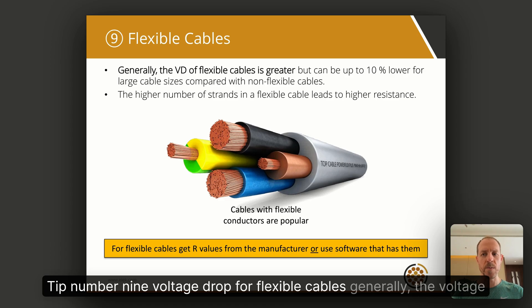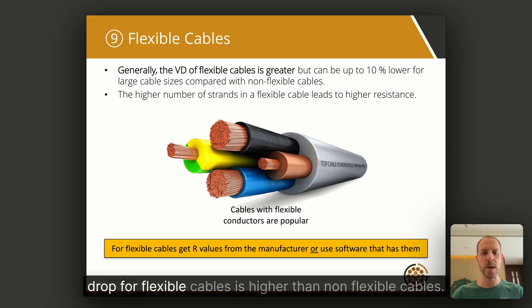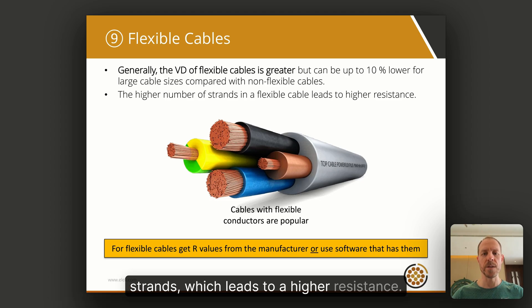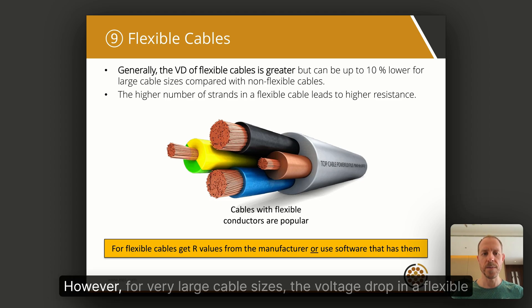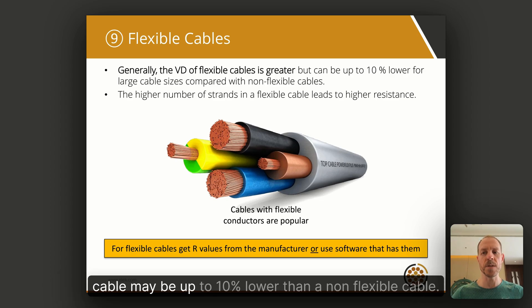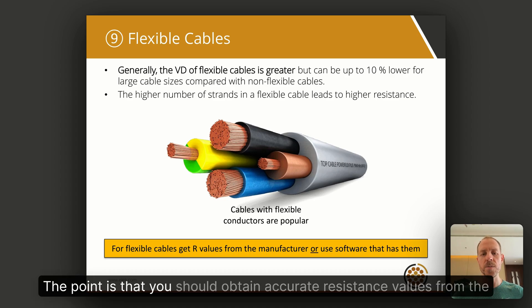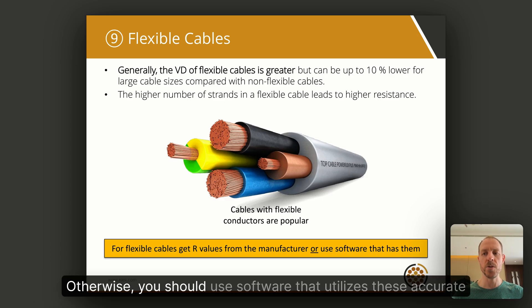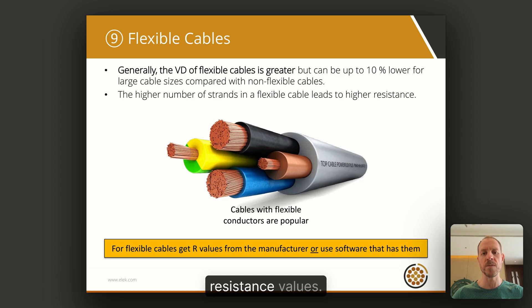Tip number nine: voltage drop for flexible cables. Generally, the voltage drop for flexible cables is higher than non-flexible cables because flexible cables have a higher number of conductor strands, which leads to a higher resistance. However, for very large cable sizes, the voltage drop in a flexible cable may be up to 10 percent lower than a non-flexible cable. You should obtain accurate resistance values from the manufacturer for flexible cables, or use software that utilizes these accurate resistance values.